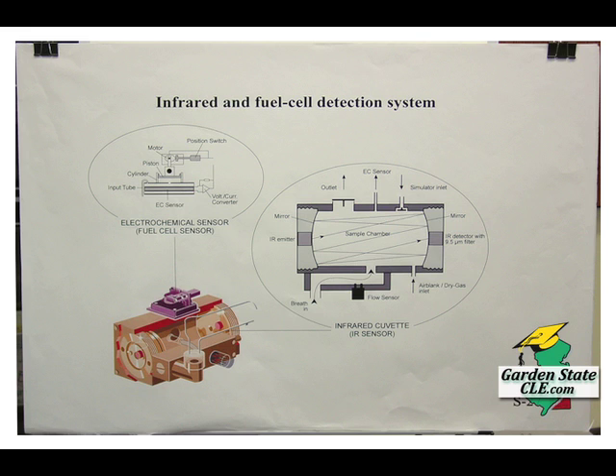It's at 9.5 microns. So basically, this is what the inside of the chamber looks like. There's a parabolic mirror on each side to reflect the light, because otherwise you'd have to send the signal down a very long path. So it's a front-coated parabolic mirror, a gold-plated mirror, and the signal bounces back and forth. And there's an infrared generator and an infrared receiver.